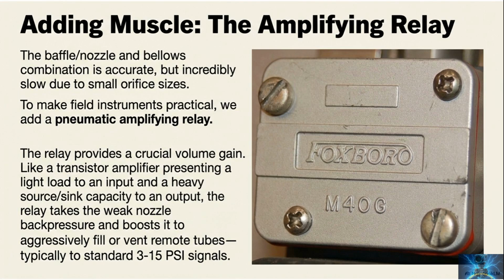Adding muscle, the amplifying relay. The baffle, nozzle, and bellows combination can be very accurate, but it is slow because the orifices are tiny. To make it practical in the field, we add a pneumatic amplifying relay. The relay gives volume gain, meaning it can aggressively fill or vent longer tubes without loading the delicate nozzle signal. It's like an amplifier that barely sips from the input but can deliver real muscle at the output. The result is a strong output signal, typically standardized to 3 to 15 pounds per square inch.